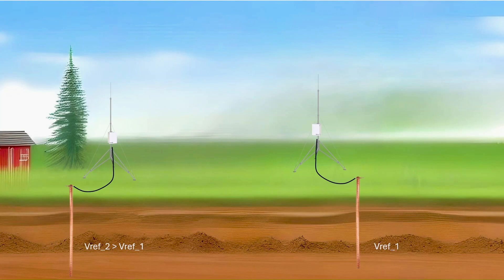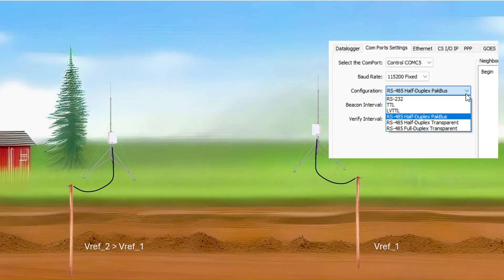I want to create an RS-485 communication link between them, so I use Device Configuration Utility to change the CR-1000X COM-C5 settings to RS-485 half-duplex PakBus with a baud rate of 115,200.